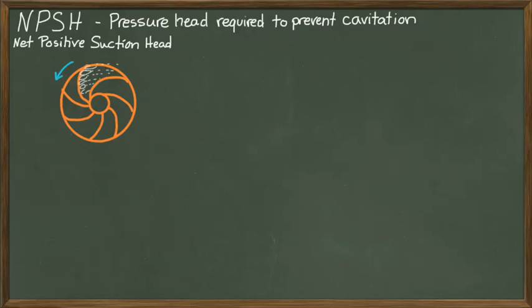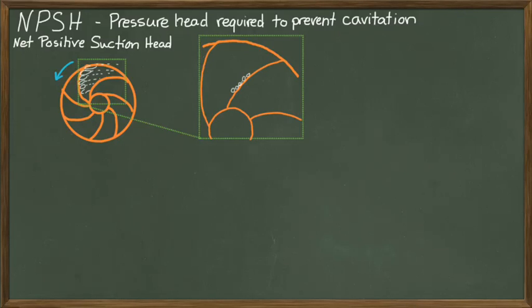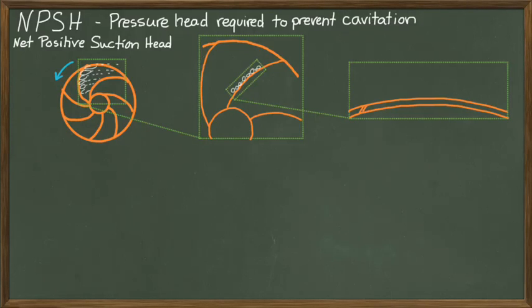This definition of cavitation by itself is not a problem for pumps. The problem starts as the next impeller blade, the one that's trailing the first, is catching the bubbles that are created. On the surface of the impeller blade, the bubbles can be compressed until the point of collapse. At the moment of collapse, a micro-jet of water forms and strikes the surface of the impeller at a velocity greater than 100 meters per second. This process, though happening on a micro-level, can begin to pit the metal surface of the impeller blade when you consider that these bubbles are forming and exploding at the rate of hundreds or thousands of mini-explosions per second.